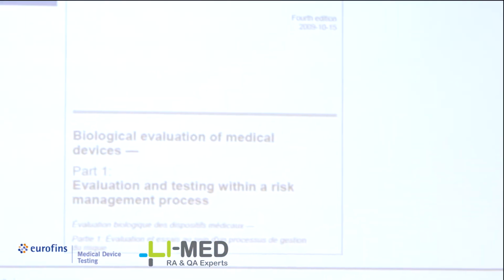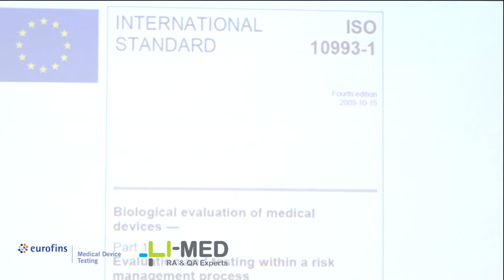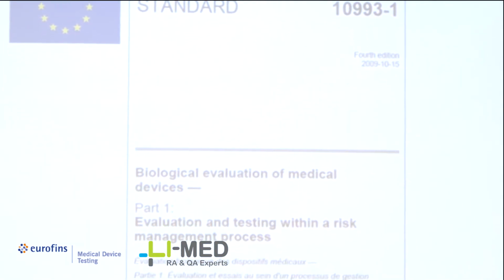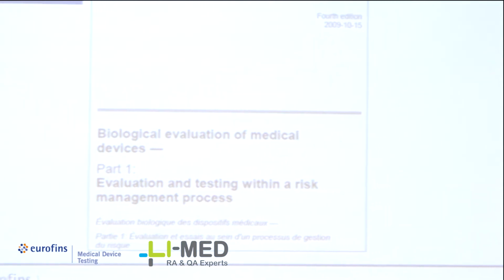That's why the ISO 10993-1 standard is really important, because according to the regulation it is considered the state of the art in terms of biocompatibility assessment. So basically there is no real good reason not to use this standard to demonstrate the safety of a device. Because basically, if a medical device is in compliance with the ISO 10993 series, the manufacturer obtains the presumption of conformity to the general safety requirements of the European regulation. And so this standard is really important in Europe, but it's also really important for the US because it's also in this case considered the state of the art for biocompatibility assessment.